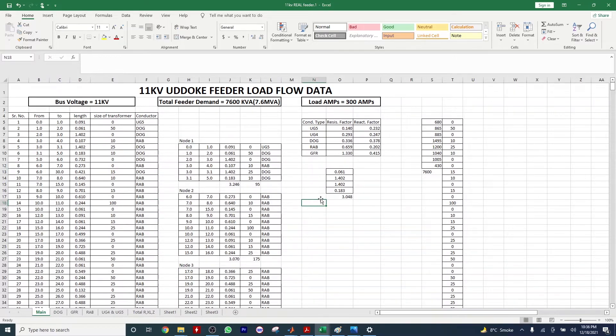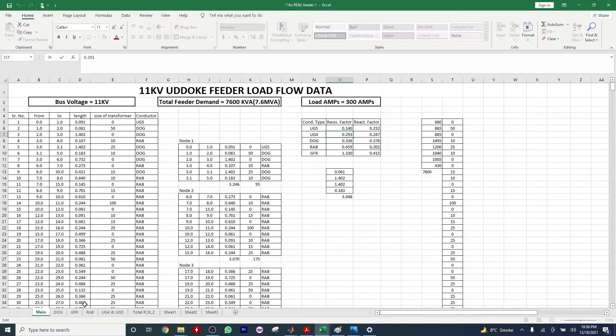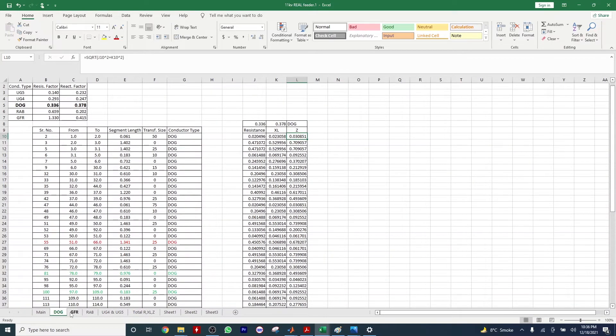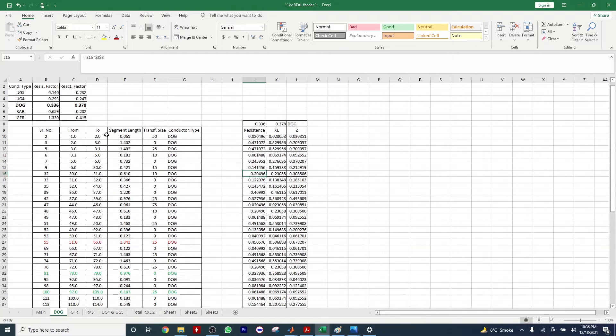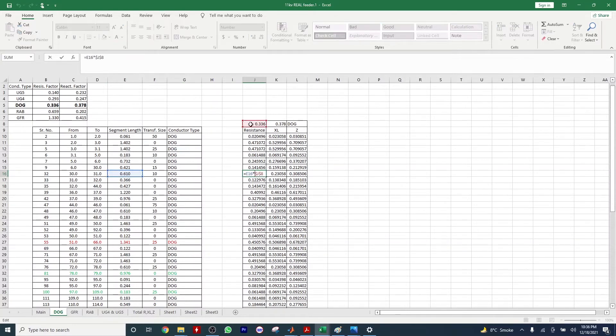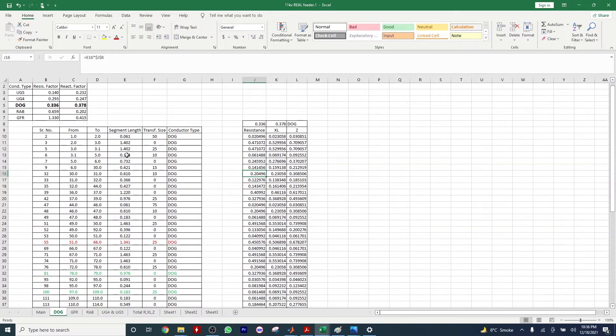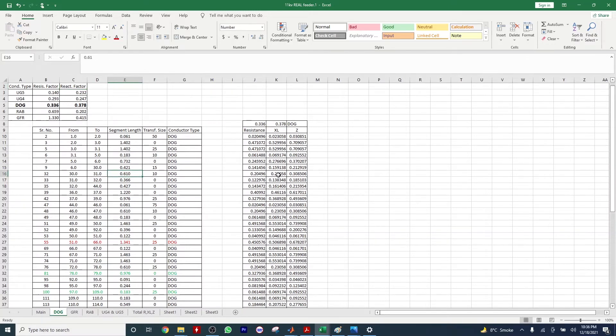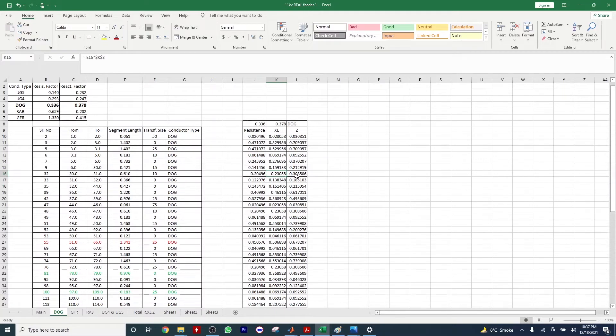If you want to calculate the resistance and reactance, it's not a tough job, it's easy. Here we have resistance factor. To calculate the resistance, we multiply the segment length with this resistance factor. To calculate the reactance, we do the multiplication of the reactance factor with the segment length.